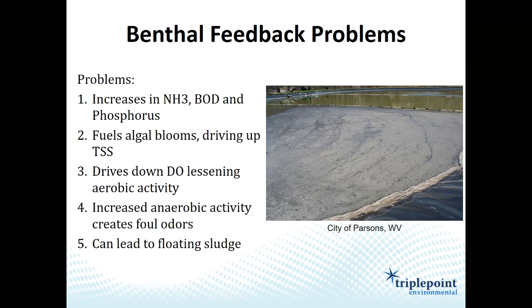You can often spot too much sludge by looking for floating or 'popping' sludge on the surface. What happens is the sludge breaks down on the bottom and releases H2S — hydrogen sulfide — which gets trapped underneath the sludge layer and actually floats it to the surface. This can fuel algal blooms, cause foul odors, and as you can see in this picture, in severe cases, this is probably some of the worst popping sludge I've seen at a facility.